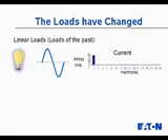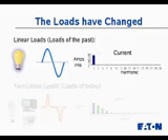Looking at the loads of the past — linear loads — what 'linear' means is that the current draw and voltage draw have a linear relationship with each other. The incandescent light bulb is a prime example: if you increase the voltage on the bulb, the bulb becomes brighter, current draw goes up, watt draw goes up; decrease voltage and watt draw goes down and current draw goes down. The graph to the right shows the current spectrum breakdown, showing us the current in a frequency realm. When we look at this, we're only seeing the fundamental frequency — which here in the US is 60 Hz.